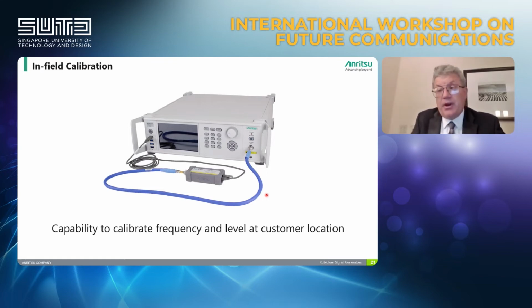to the factory. And it's very important in many specific, very sensitive applications when you cannot just send the unit back to the factory often for recalibration. You can do it right at your facility, which is again very important in some applications, and also simply convenient for the end user, and it simplifies the recalibration process.